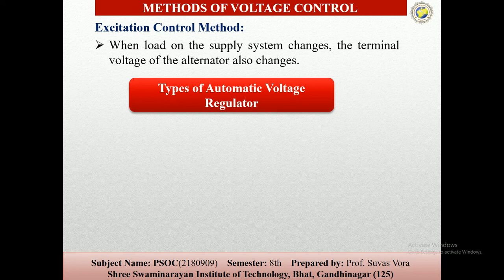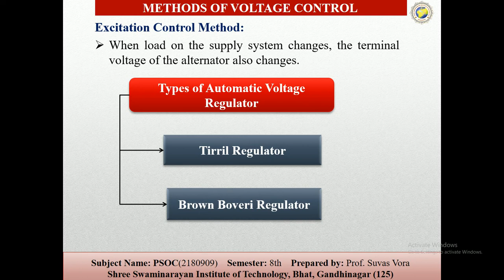But the controller has two types of automatic voltage regulation systems. The first one is the Tirril regulator and the other is the Brown-Boveri regulator. Now the first one is the Tirril regulator. In this type of regulator, a constant value resistance is cut in and cut out of the field circuit of the alternator by using tap changing.